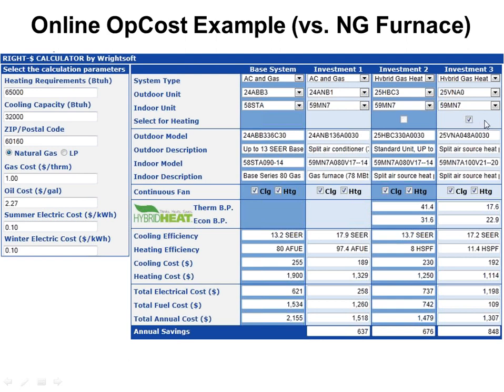Other 2 things to note on this software, there's this little checkbox that says select for heating. It only pops up if you put a heat pump in here, and it's only allowed to be checked if you put in a variable speed heat pump. What that does is tries to upsize the heat pump one size. So I had a 32,000 BTU cooling load, so you would have thought that I would have put in a 2.5 or 3-ton unit. I guess a 3-ton because I don't have a 2.5 on the variable speed. But this guy put in a 4-ton heat pump in this software. He basically upsized him for the heating mode to get more hours. The other thing you'll notice is that the software gives you the thermal and economic breakpoints.